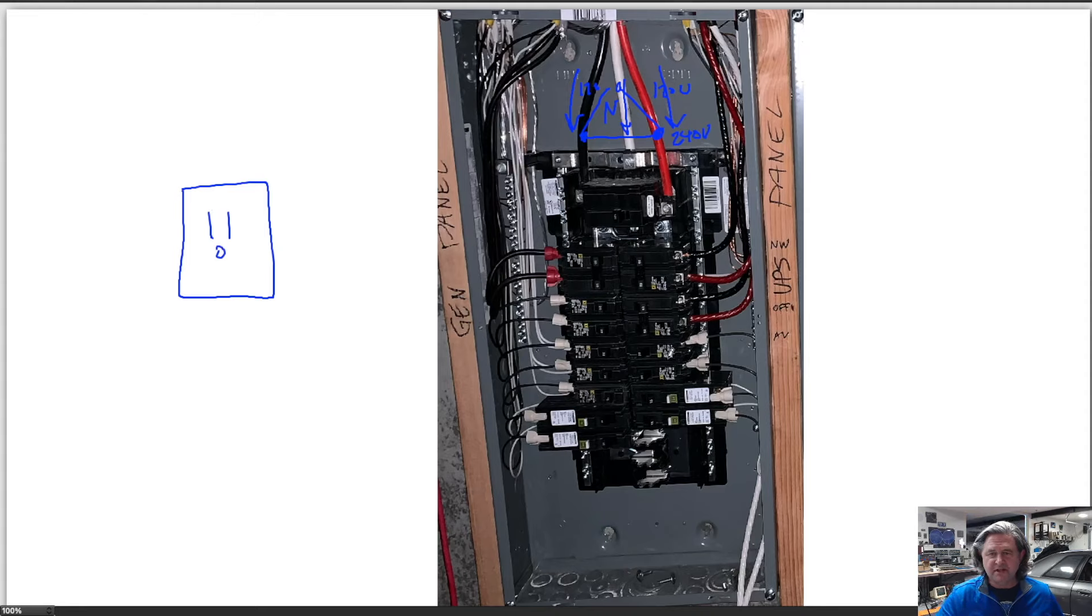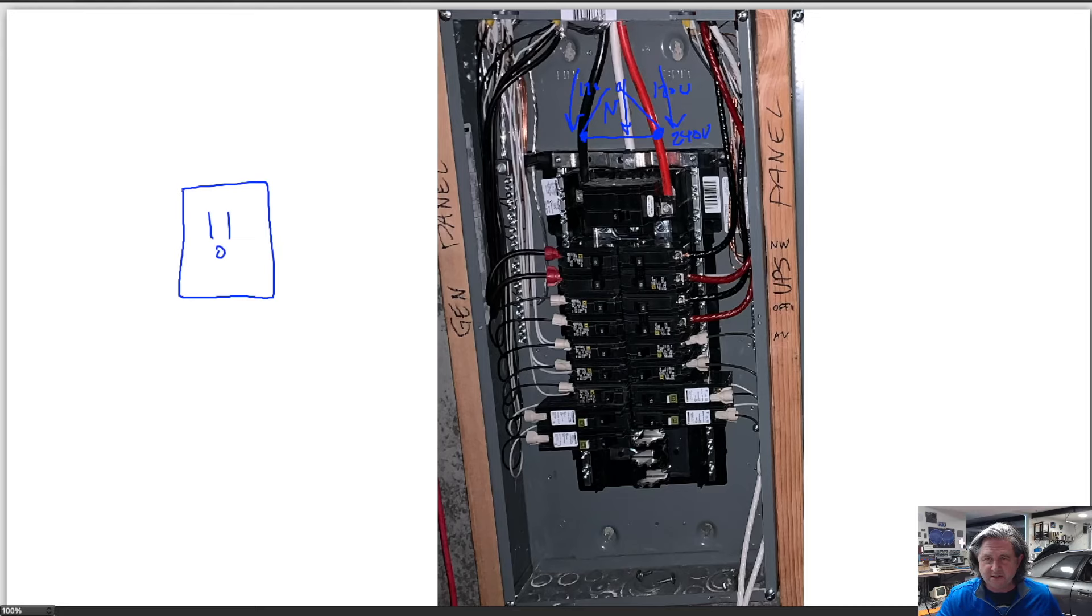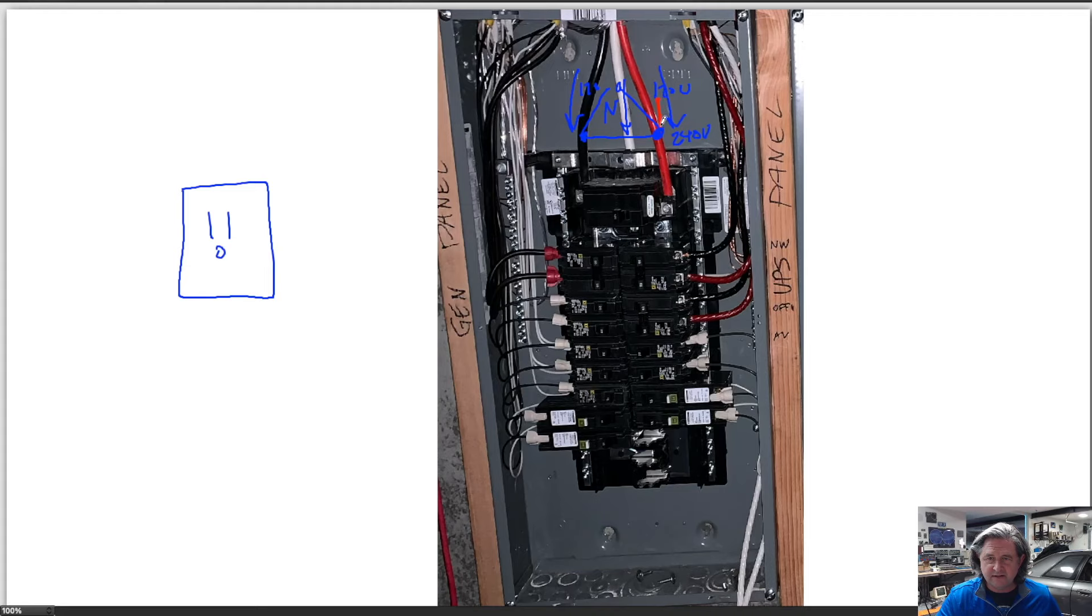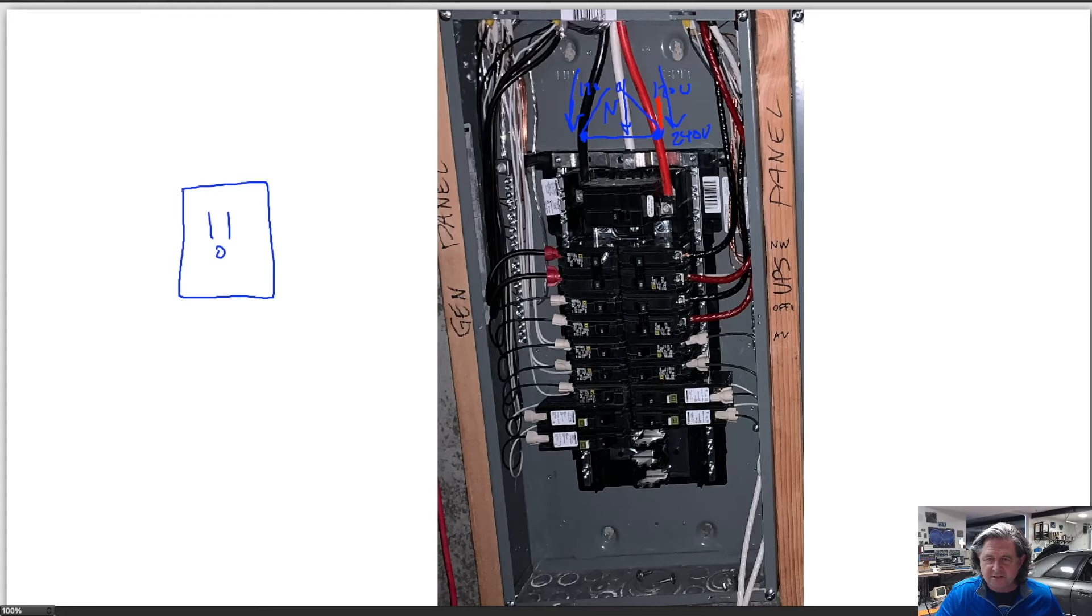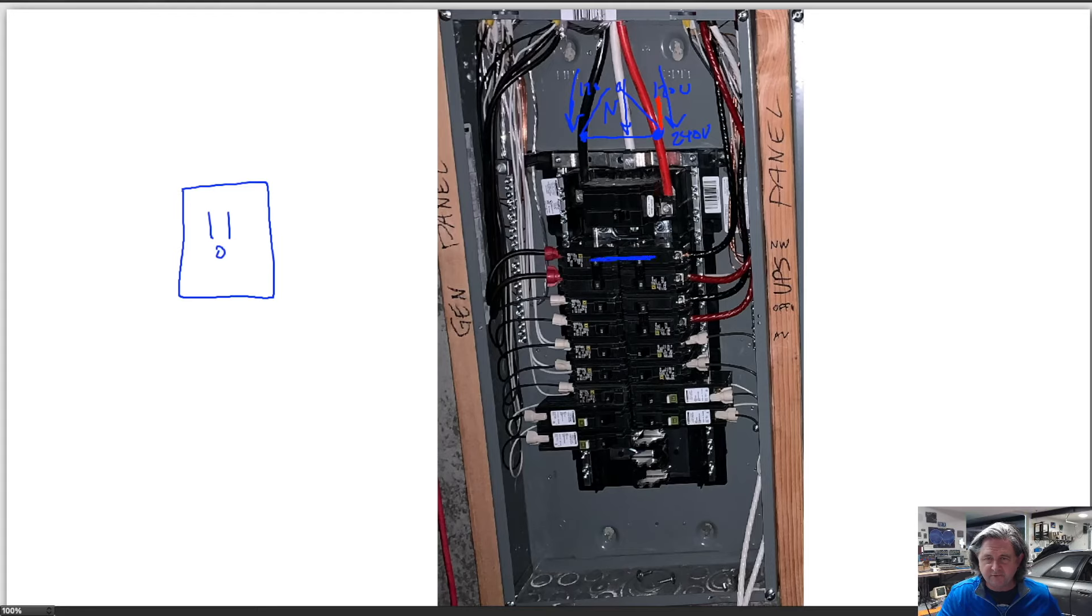The panels themselves are kind of organized to have a neat way they're done such that we'll say that we're going to call this the red phase and then we have the blue phase over here. They're done such that the breakers that are across from each other in one row are the same from the same phase and then it skips a row and then the same phase and then skips a row in the same phase. Then the next row below it is the other phase.